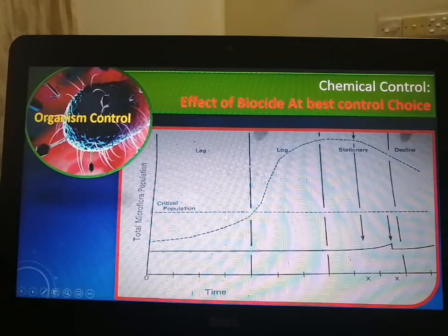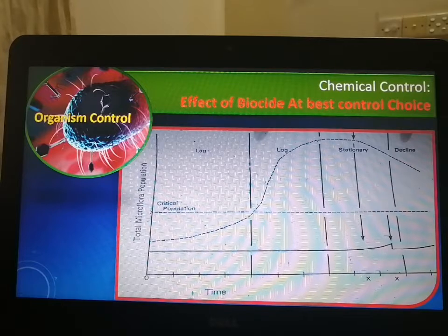So if we want to be successful in controlling microorganisms in any system, we can't allow the number of microorganisms at any point of time in my treatment system, around the year, to grow above this number. So if a product gives a result like this, which is much lower than the critical population number, but after a certain time it goes up again, if we understand it is growing, we can slightly increase the continuous dosing, and again it will come down and go further. This is a very good example of continuous dosing biocide, where we can keep the organism very well controlled.